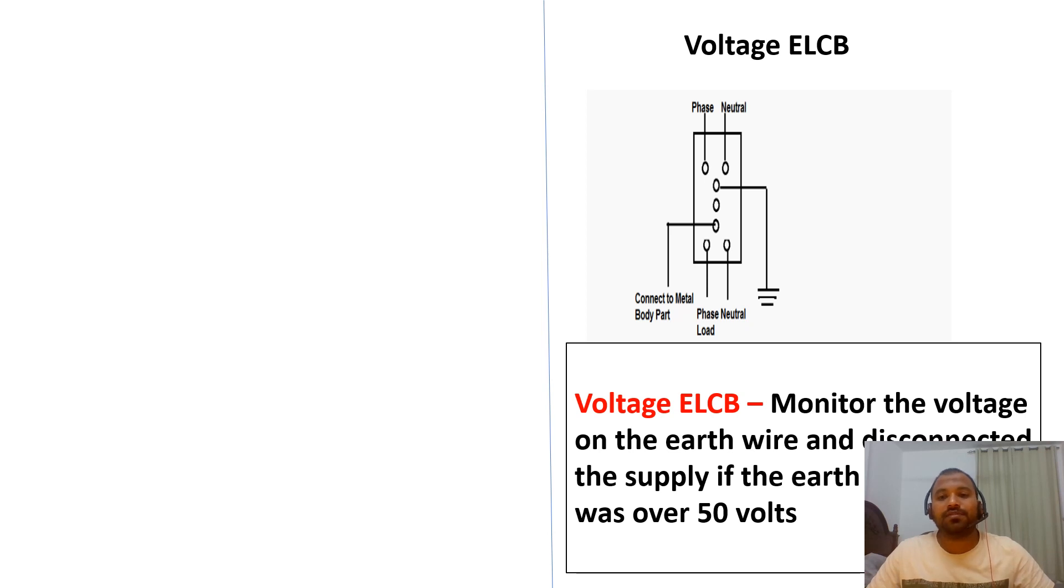These ELCBs monitor the voltage on the earth wire. This earth wire voltage is monitored. When there is a leakage current which exceeds 50 volts, then this voltage ELCB senses it and will trip the breaker.